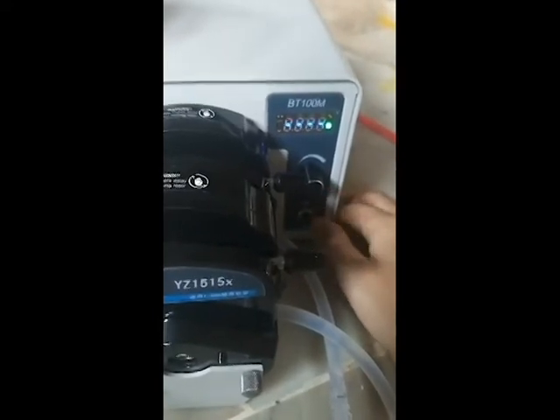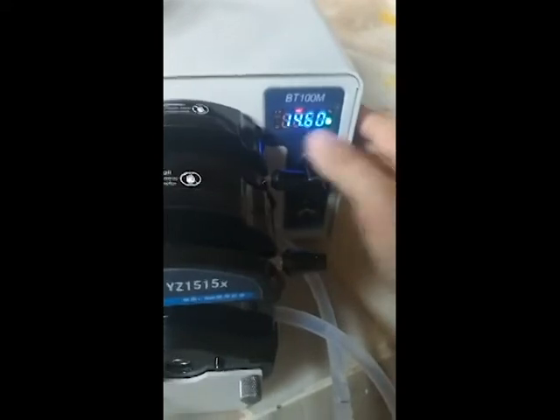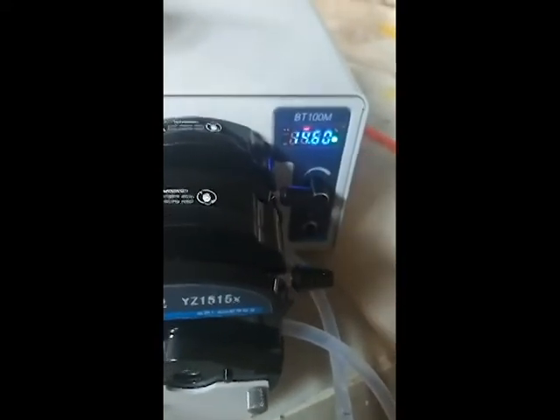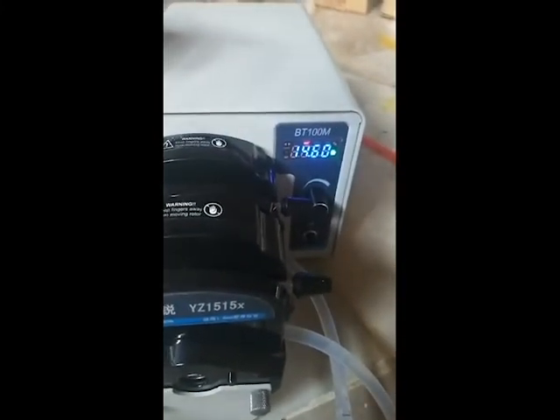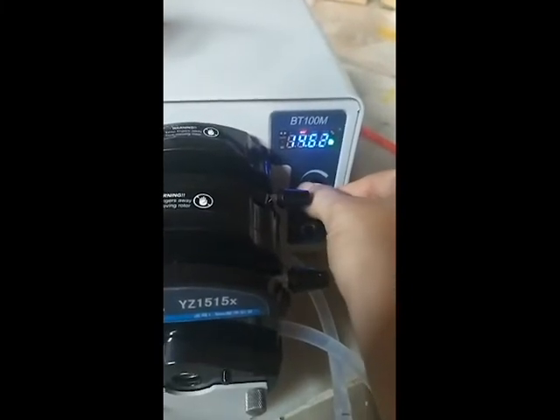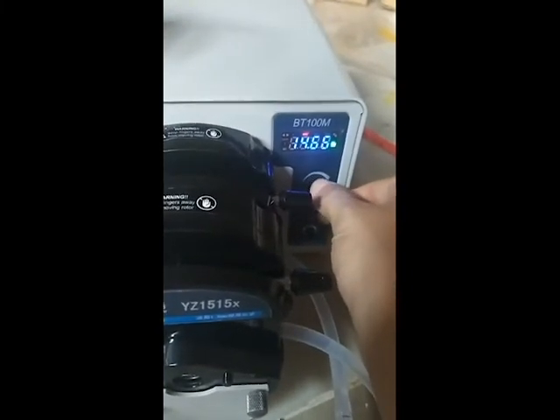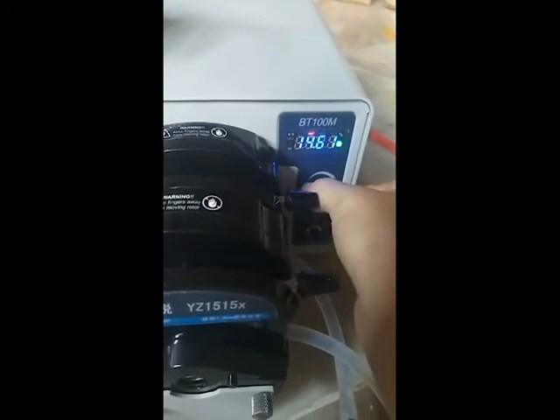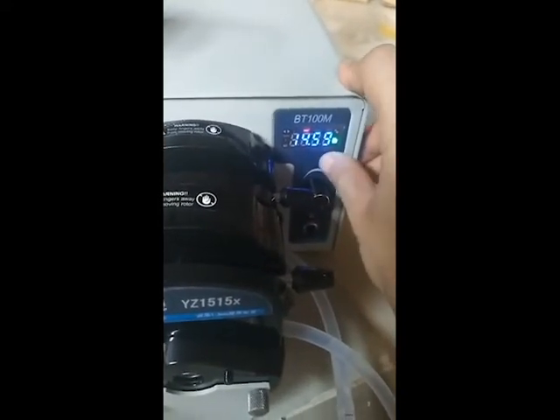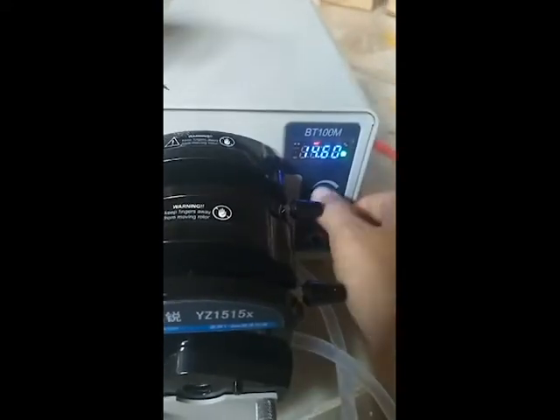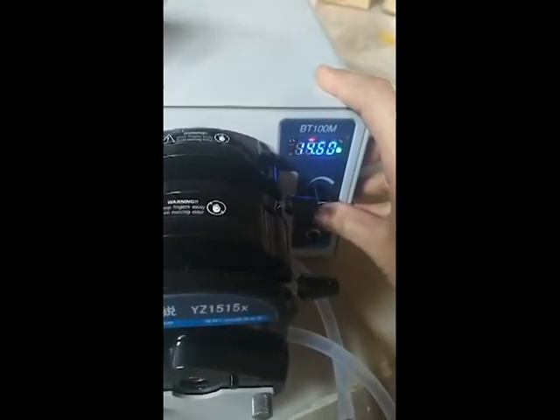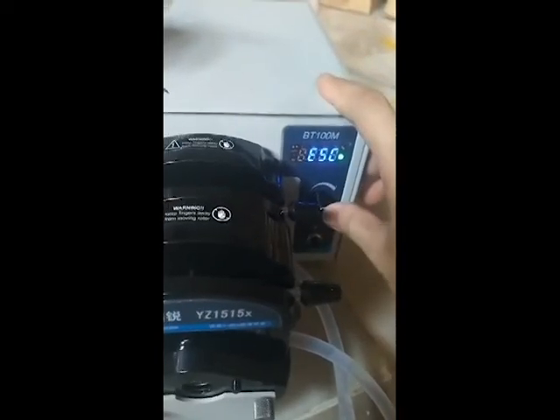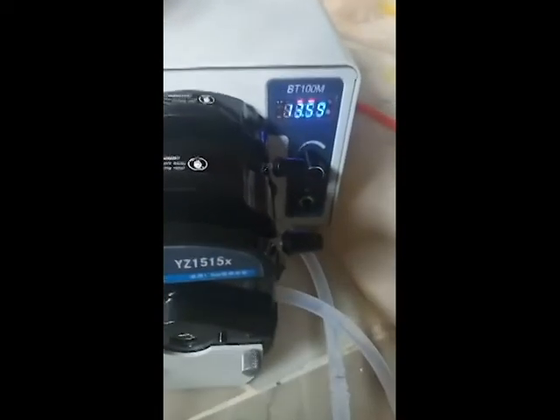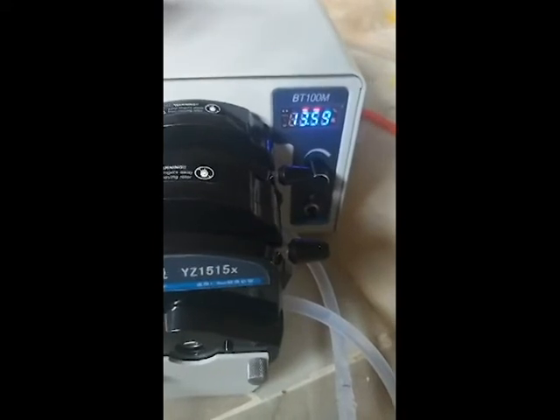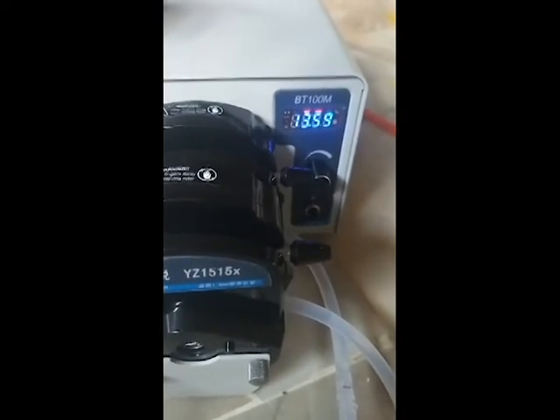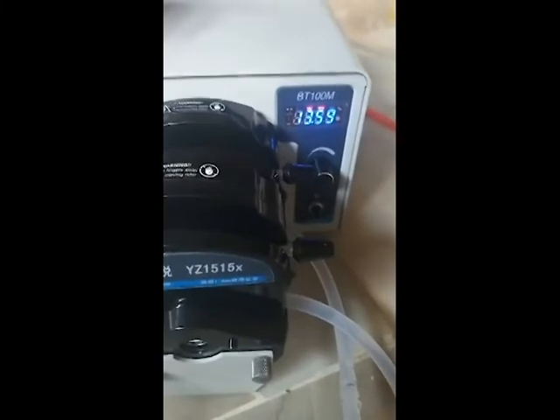At this moment, you can stop the pump. Then this value is the real volume of your calibrated volume. You can key in the real value by rotating and decreasing its value to your real calibrated value. After that, you confirm your calibrated value and click ESC to go out. I will do the calibration together with you when we conduct our training. If you have any problem, you can contact us.